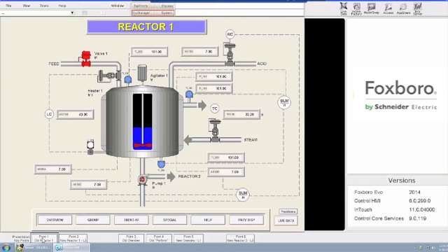Here is a very typical example of a graphic you might find in any plant running today. As you can see, it was designed based on a P&ID. The indication readouts are situated near their corresponding measurement probes. The tank is pretty and three-dimensional, and the valves have a lot of detail. But there are several problems with this style of graphic, which can negatively impact operations.